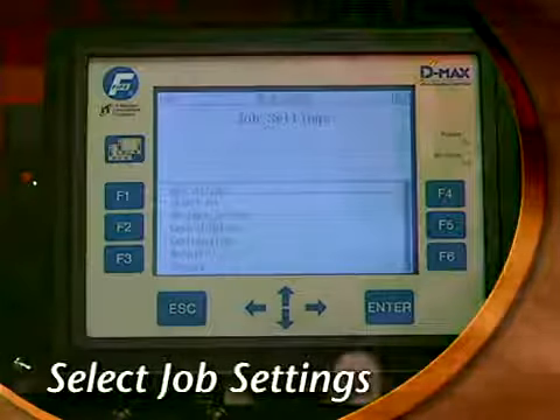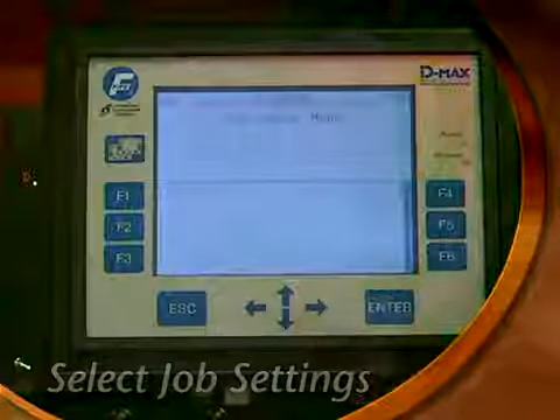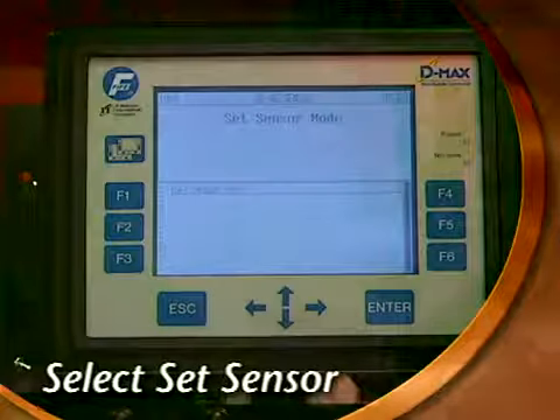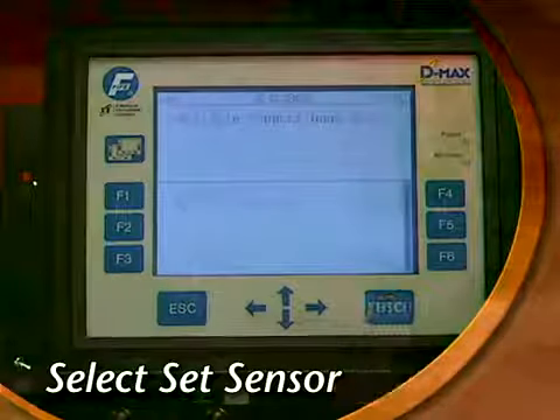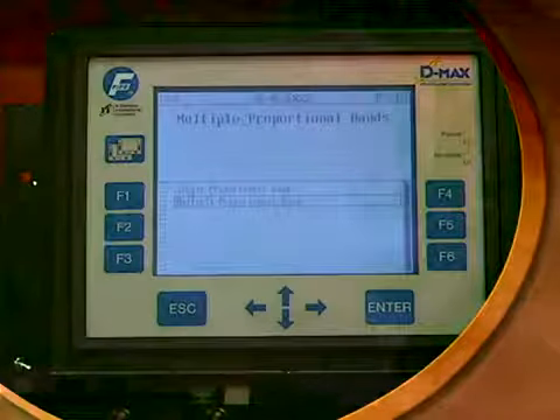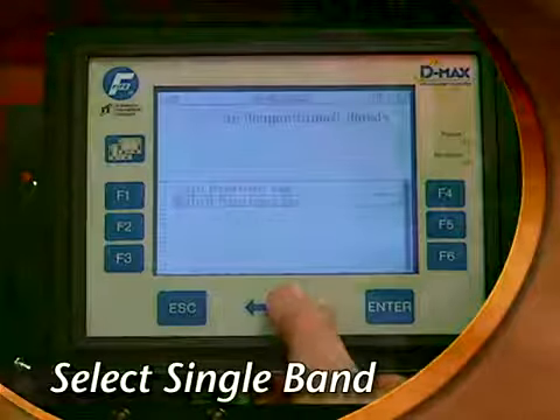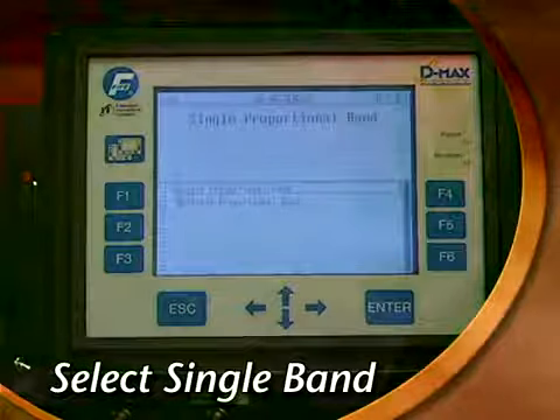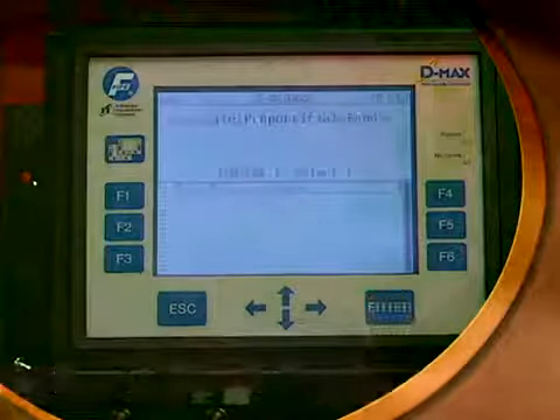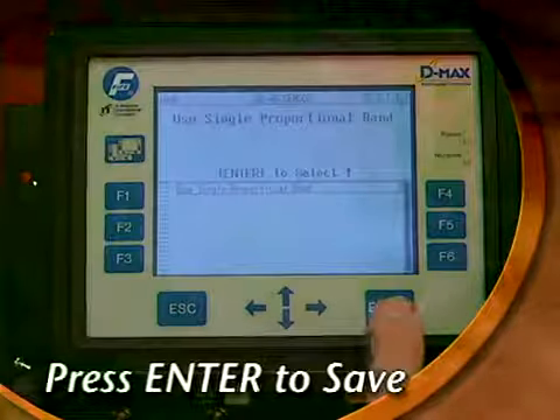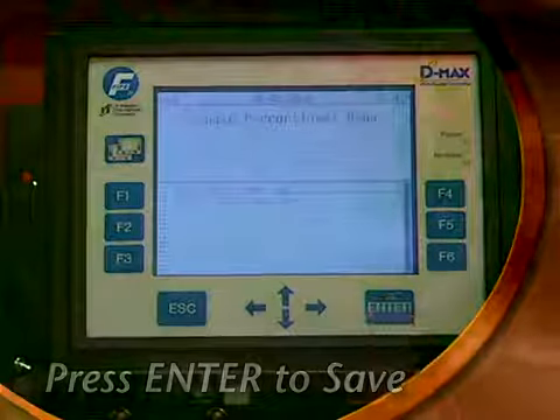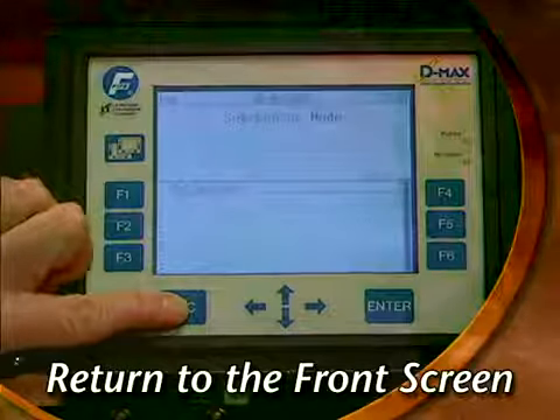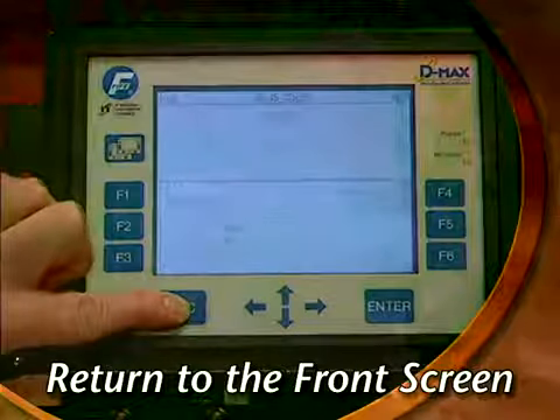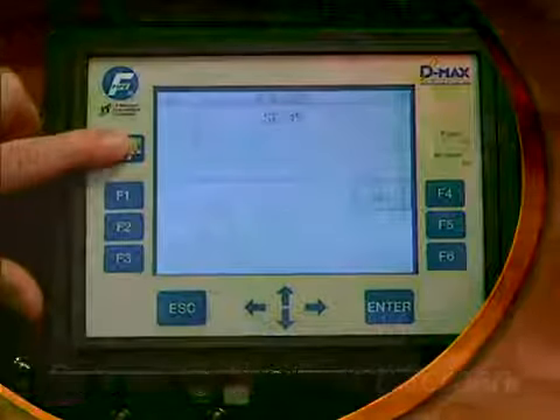Select the Job Settings option and press Enter. There's only one mode, Set Sensor, so press Enter again. Select Single Proportional Band and press Enter. Press Enter again to save. Press Escape 3 times to return to the front screen and then press the Page key to complete the setup.